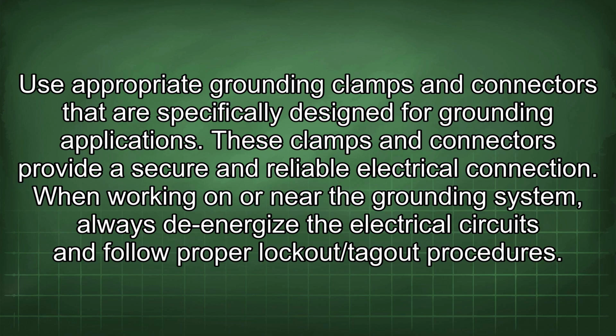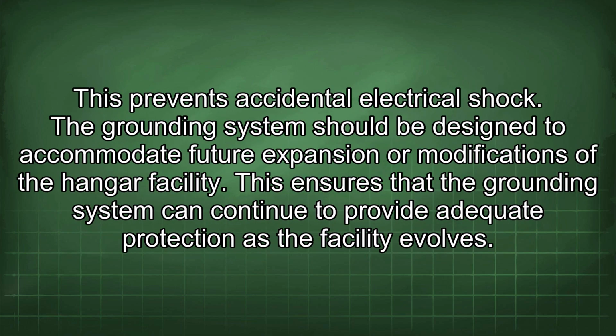When working on or near the grounding system, always de-energize the electrical circuits and follow proper lockout/tagout procedures. This prevents accidental electrical shock. The grounding system should be designed to accommodate future expansion or modifications of the hangar facility. This ensures that the grounding system can continue to provide adequate protection as the facility evolves.